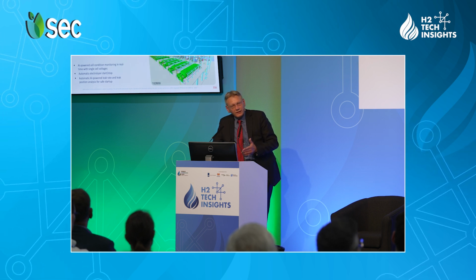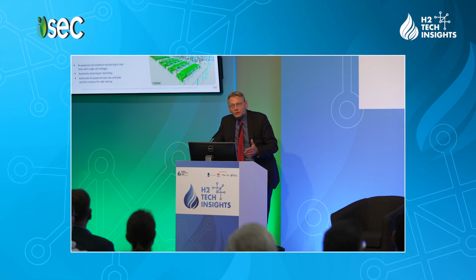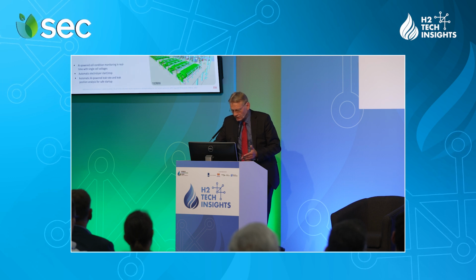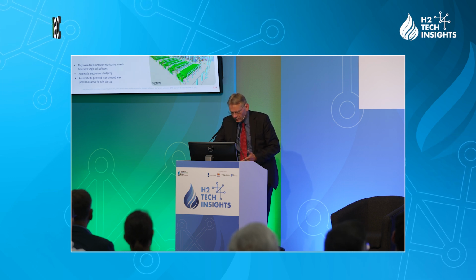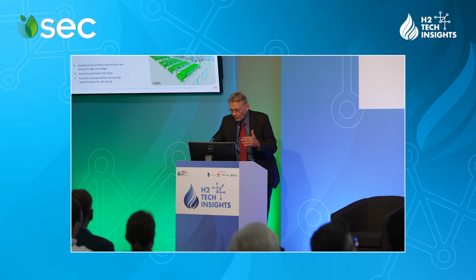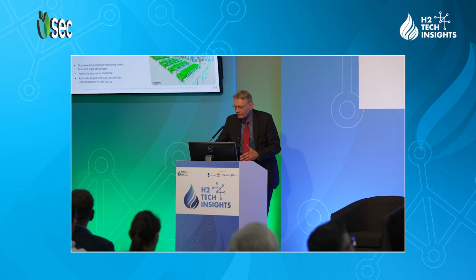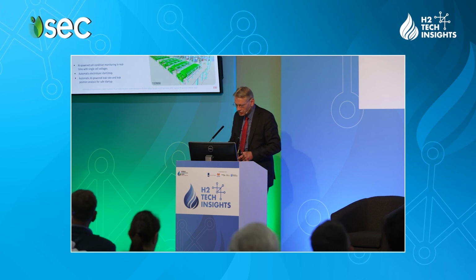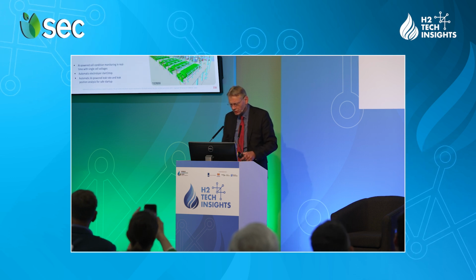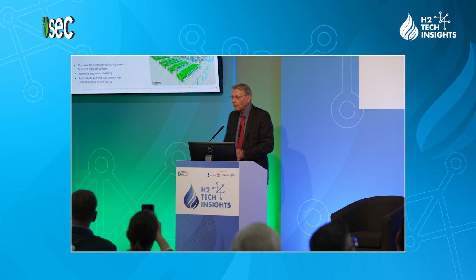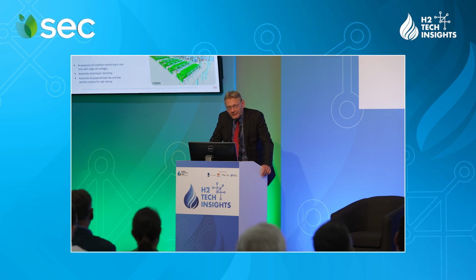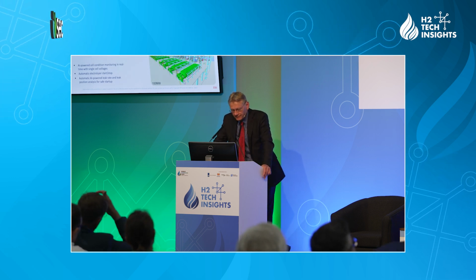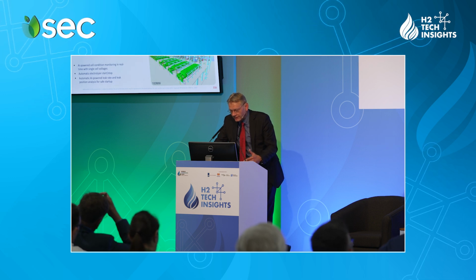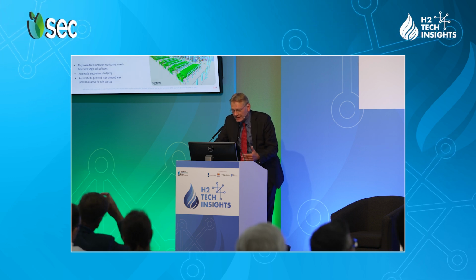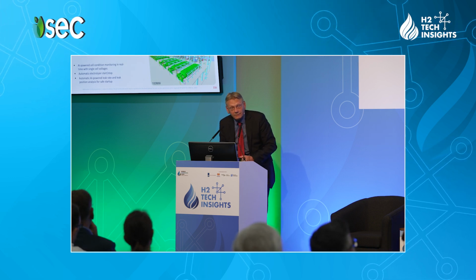Green energy powered electrochemical plants, they will have to stop an electrolyzer when the sun goes down and the wind slows down. So for electrolyzer in operation, you have state-of-the-art single voltage based solutions for safety, condition monitoring and performance prediction. But for fully automatic electrolyzer operation, an AI-powered leak rate and leak position analysis is needed to have a safe startup.